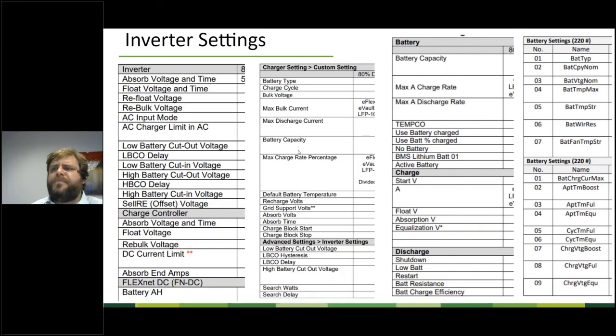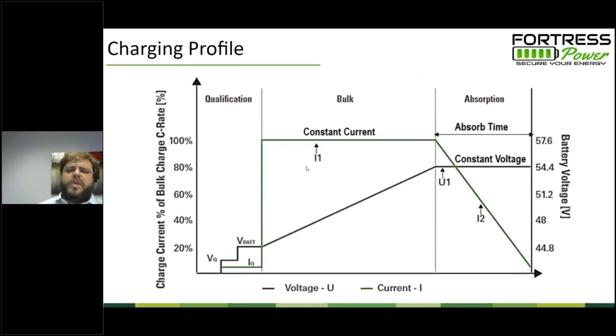And lithium ion batteries are a little bit different than lead acid in that they don't really use a 3-stage charge cycle of bulk, absorb, and float. They really use just a more simple 2-stage charge cycle, which is a fast bulk charge from a low percent state of charge up to near the top, and then a more gentle absorb charge to get those cells all the way to their fullest potential.